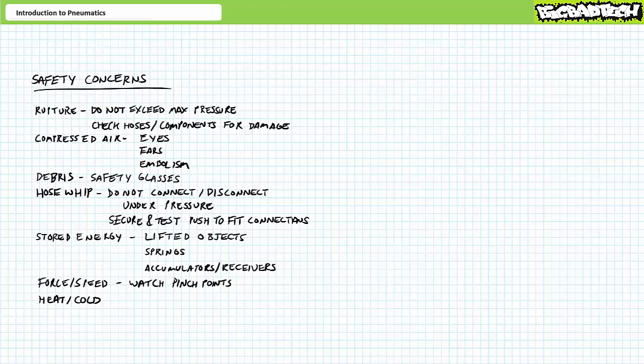A common application for fluid power systems in industrial settings is to lift or suspend heavy objects. A lifted or suspended object itself represents stored energy, as does the fluid under pressure supporting them. These need to be taken into consideration when performing maintenance on these types of systems and those lifted or suspended objects need to be lowered or blocked out and the pressure relieved from the system before maintenance operation can begin. Additionally, components such as accumulators or receivers or springs can store energy in a fluid power system and must be released and locked out prior to performing maintenance.